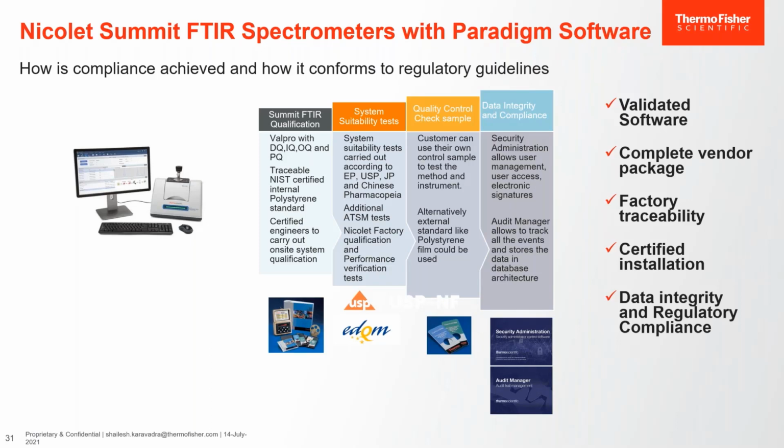This slide shows how our entry-level Nicolet Summit FTIR spectrometer with Paradigm software is compliant. We do FTIR qualification with our ValPro package, which includes design qualification, installation qualification, operational qualification, and performance qualification tests.